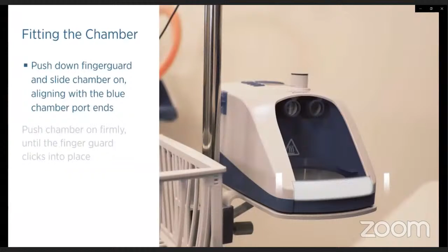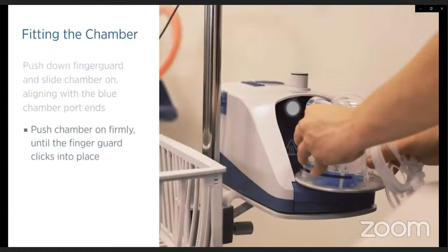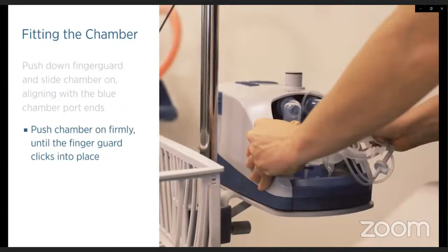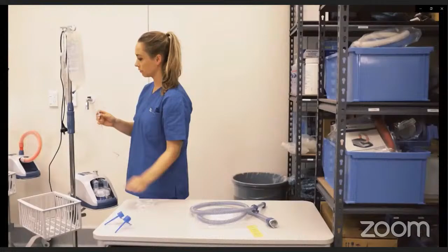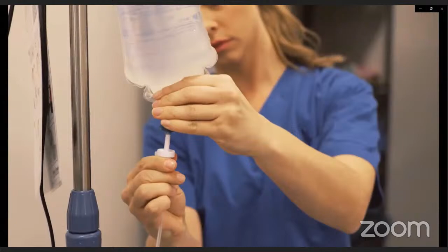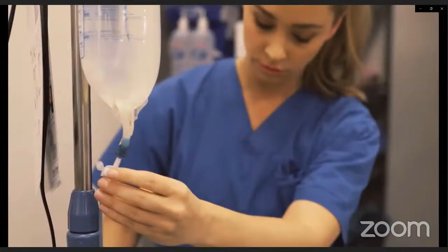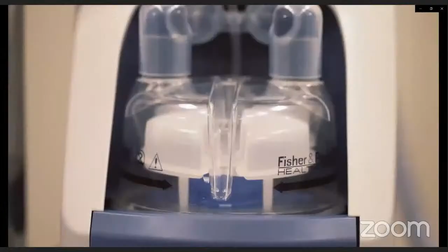Fit the water chamber to the unit by pushing down the finger guard and sliding the chamber on, carefully aligning with the blue chamber port ends. Push the chamber on firmly until the finger guard clicks into place. Attach the sterile water bag to the hanging bracket at least 20 centimeters above the unit and push the bag spike into the fitting at the bottom of the bag. Open the vent cap on the side of the bag spike. The chamber will now automatically fill to the required level and maintain that level until the water bag is empty.